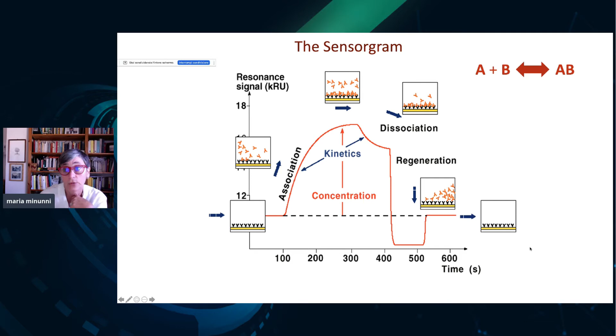It's not always obvious to come back exactly to the baseline. And this is very, very important, because if you don't come back to the same value, you have a different surface capacity at a subsequent cycle. And this affects very much the reproducibility of the measurement. So one really has to care about regeneration optimization, selecting the solution, the time, and things like that.